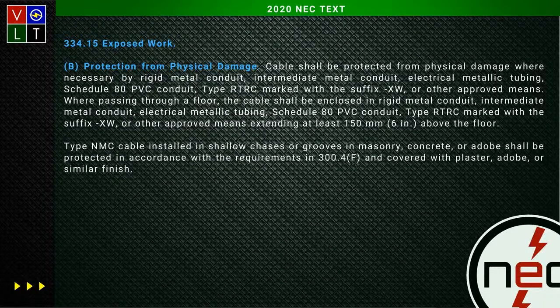I saw some of that in the comments and wanted to show people where the code actually tells you that you can do that, because some people believe non-metallic sheathed cable can never be installed in a raceway. That's not true — you can have short sections where you're protecting that cable assembly from physical damage.